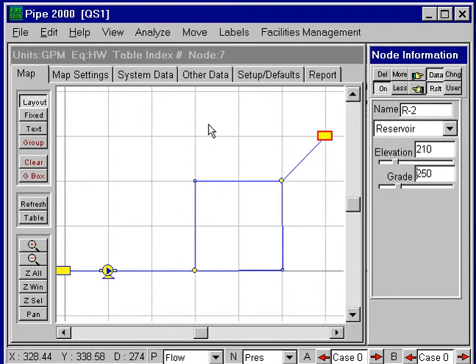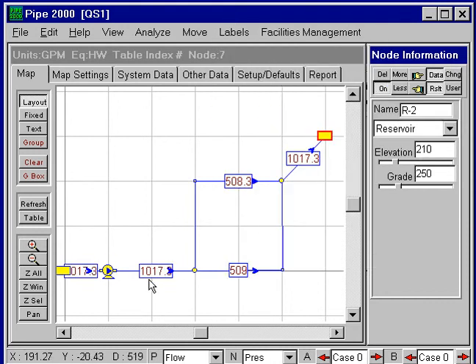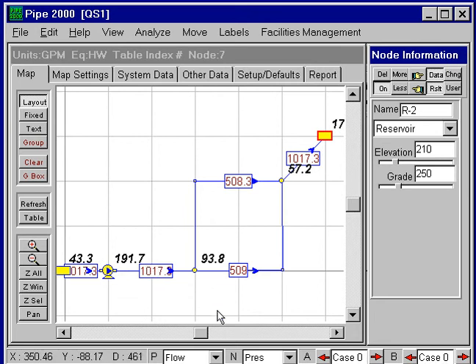I'll go ahead and use the 25-year analysis and see the results. Now I need to look at the flow rates — we have a big increase in flow rate, and the pressures will increase also because of the pump. The pressure is about 191 PSI. It's a very straightforward process to modify your system and compare results to earlier results.